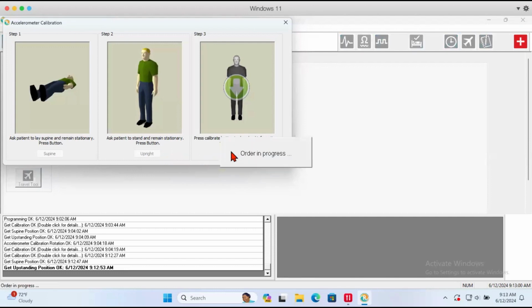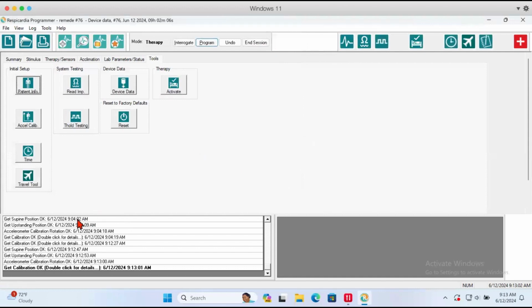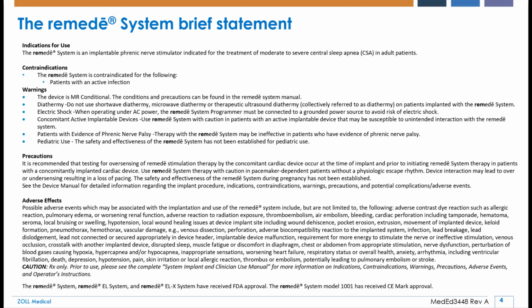Once both supine and upright positions are saved, click the calibrate button to calibrate the position sensor within the implanted device. Successful calibration is confirmed by reading accelerometer calibration rotation OK in the programmer history window in the bottom left-hand corner. These are the steps to calibrate the position sensor within the device.